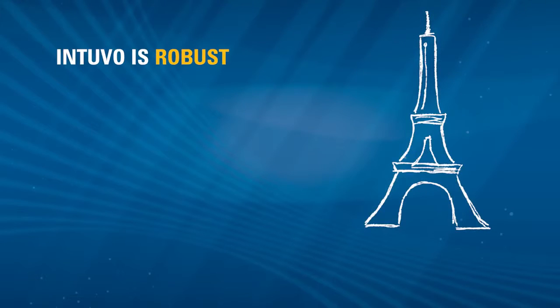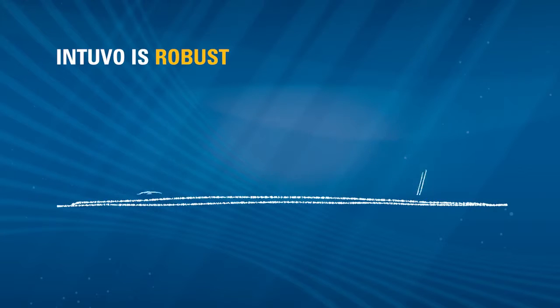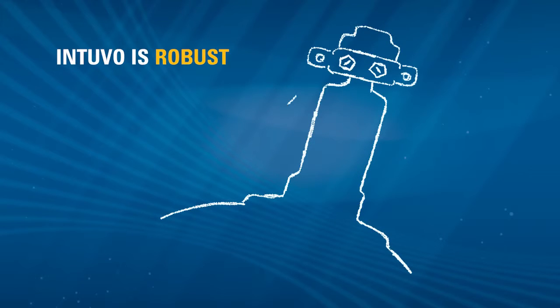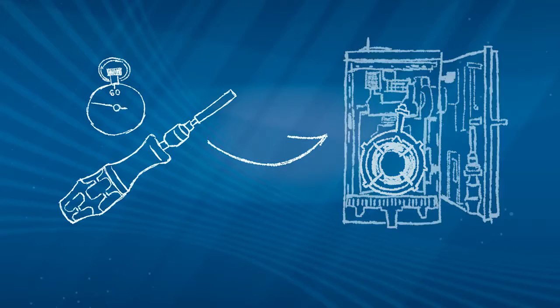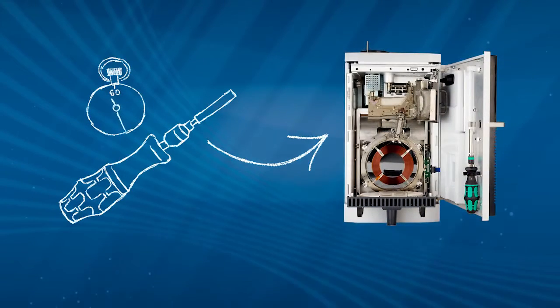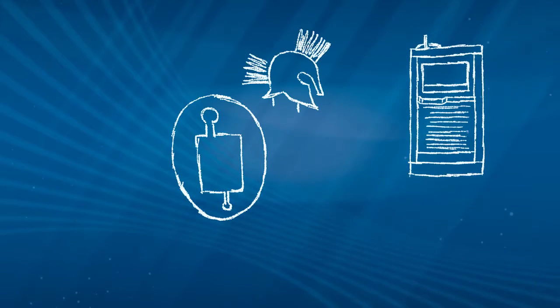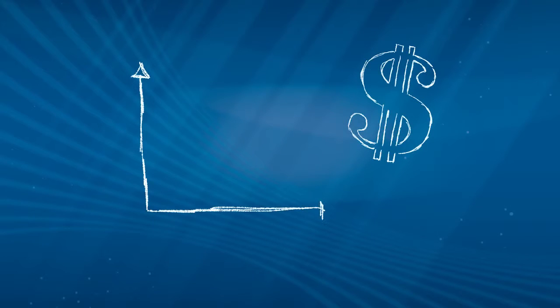Intuvo is robust. Intuvo eliminates traditional nuts and ferrules. An audible click tells you your connection is leak free. The column is replaced in less than one minute and never needs trimming. A new inert flow path offers distinct advantages. The guard chip, a disposable retention gap, protects the system from nasty sample matrices and is changed in seconds. This innovation translates into less downtime and higher productivity.